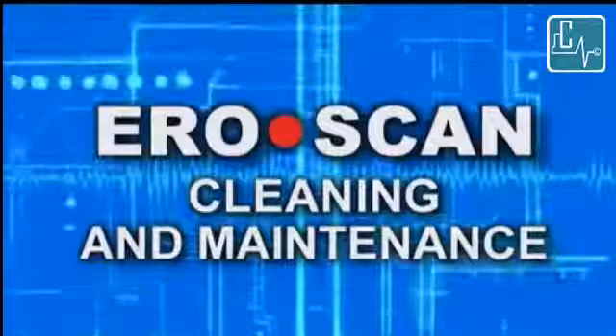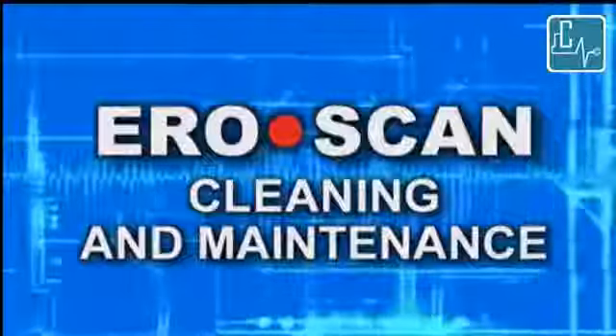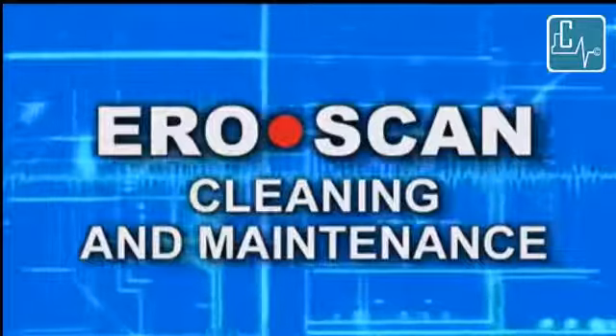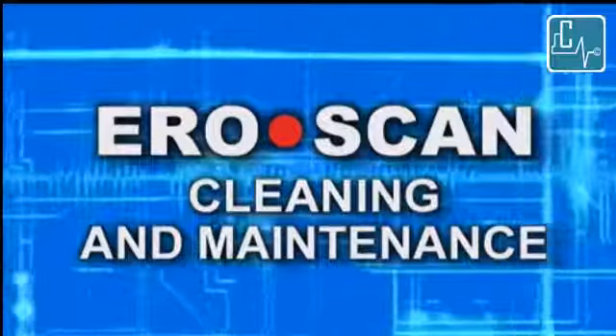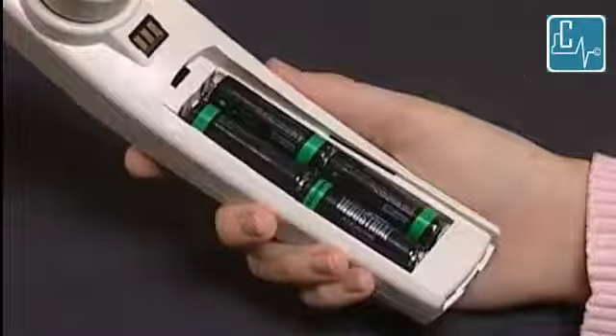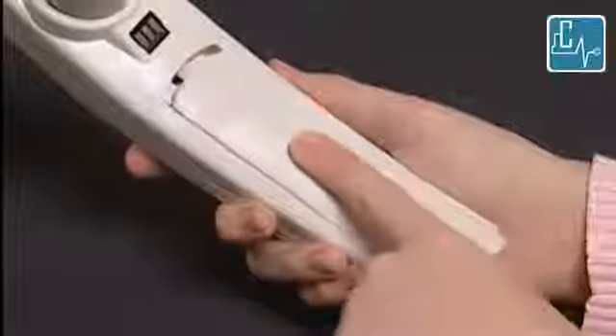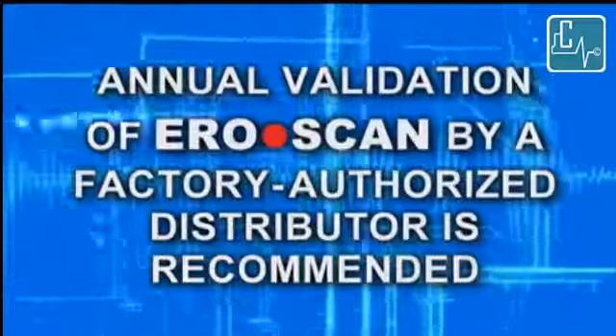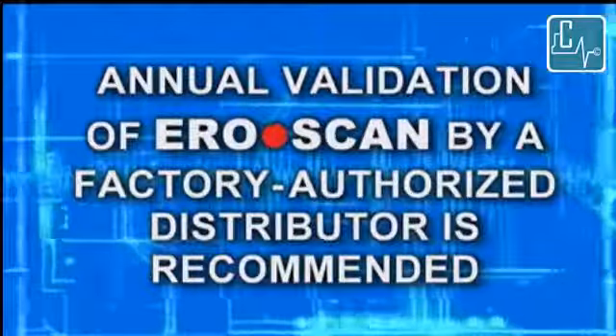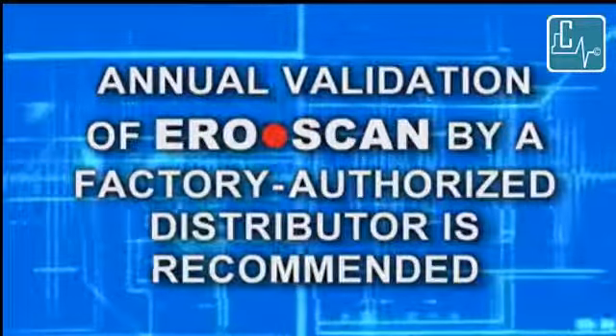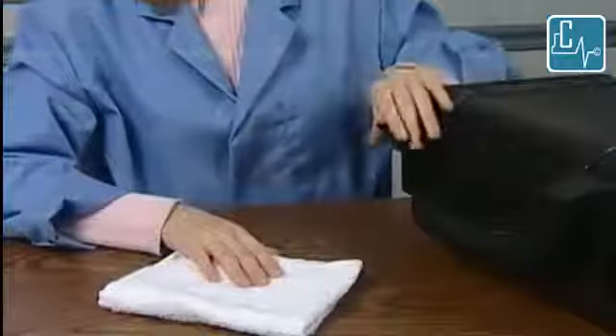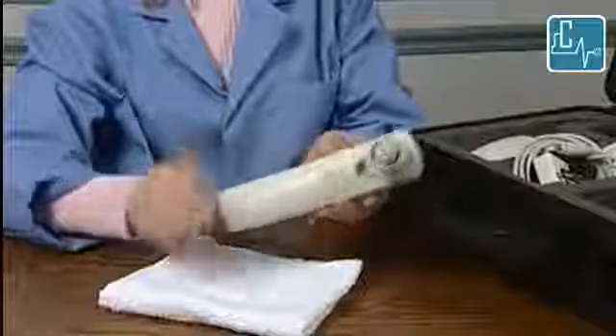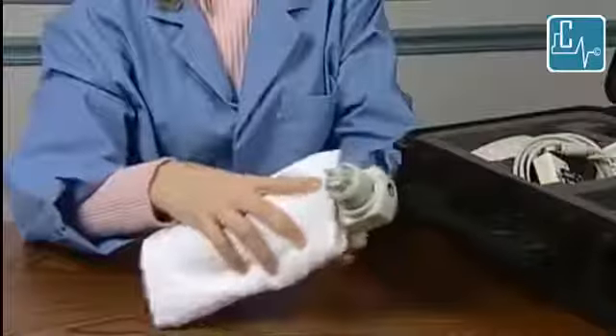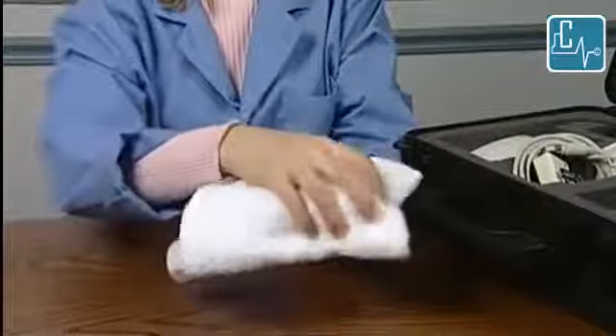Now let's cover procedures for cleaning and maintenance of the ERO.SCAN. This instrument requires no regular maintenance beyond routine cleaning and replacement of the 4 batteries in the handle of the ERO.SCAN unit. Please note that while it is not required, it is recommended that a factory-authorized distributor perform an annual validation of the ERO.SCAN. If the ERO.SCAN system needs cleaning, it may be wiped down with a damp cloth and a mild antiseptic solution such as Cetalcide.